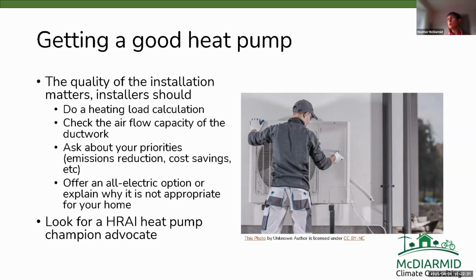Some things to look for: are they doing a heating load calculation for your home, or are they going by rule of thumb, which works fine with furnaces? The vast majority of furnaces are way oversized and people don't realize it. Are they tailoring the system to your home's needs with a heating load calculation? Are they looking at your ductwork and its airflow capacity? You want to make sure the heat pump isn't oversized for the ductwork, because that leads to noisy operation, less efficiency, and wearing out of the equipment.